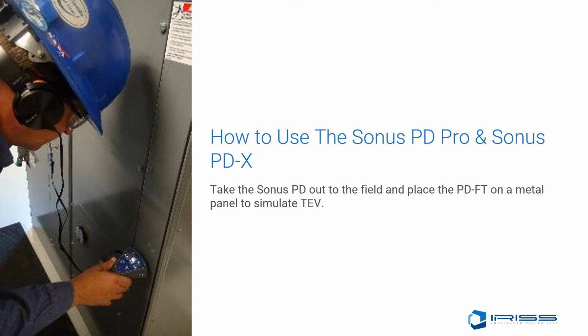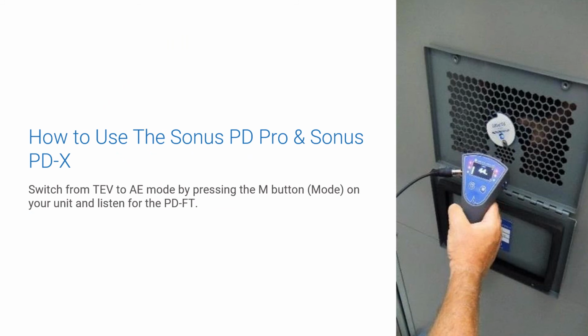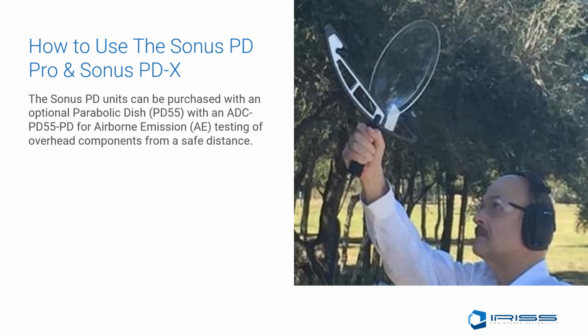Next, you can take the Sonus PD unit out to the field and place the PDFT on a metal panel to simulate TEV. Move your device around and look for the decibel value on the TEV mode to increase as you get closer to your PDFT unit. Again, switch from TEV to AE mode by pressing the M button on your unit and listen for the PDFT in the acoustic emission range, better known as ultrasound. The Sonus PD units can even be purchased with an optional parabolic dish, part number PD55, and with a cable ADC-PD55-PD for airborne ultrasound testing of overhead components from a safe distance.